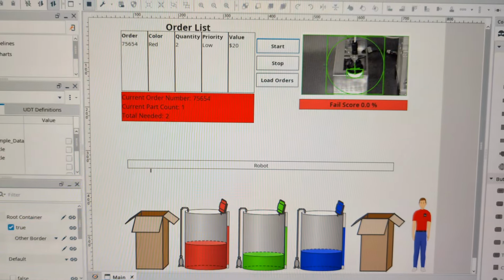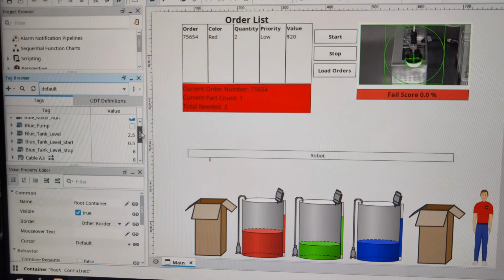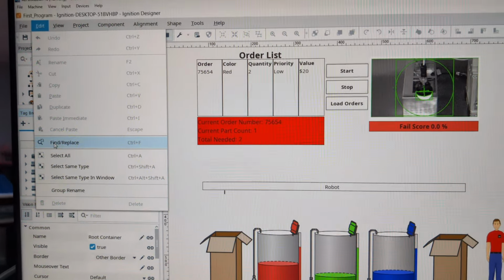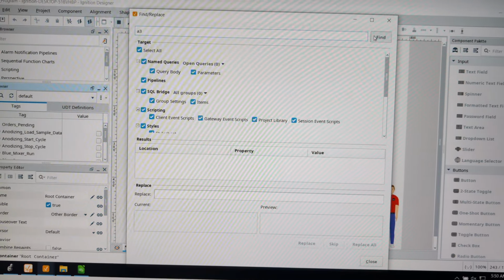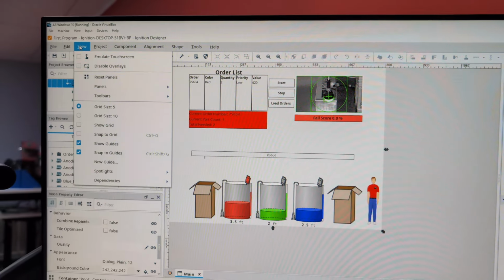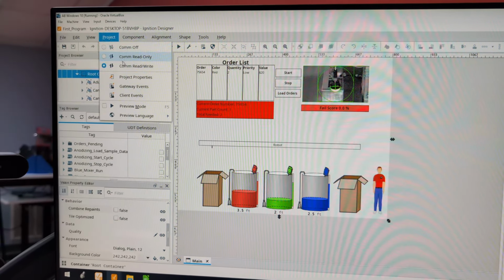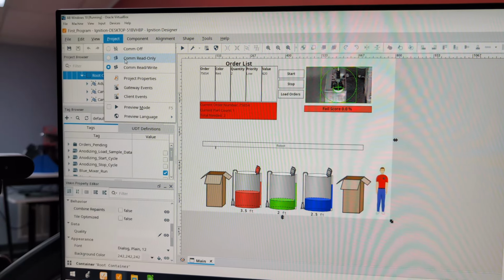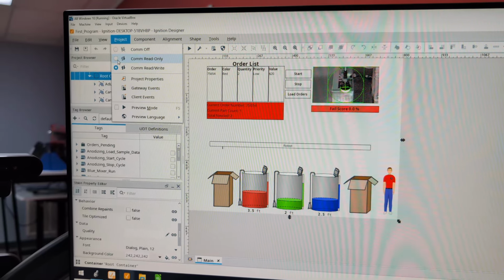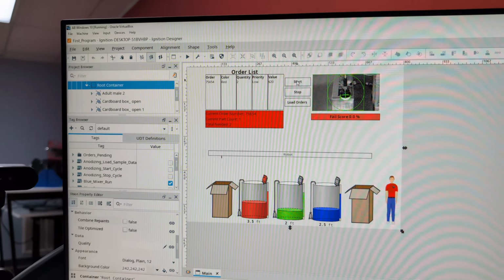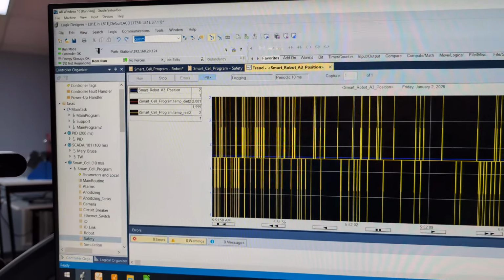Let's go over to Ignition. We know it's A3, so I'm just going to go to the edit. And we're going to find, and yeah, I'm just going to search for A3 because I believe all the instances of that would have it. Okay. So now I'd never seen a need to do this, but now would be a good time for, you know, instead of wandering through this, I should turn off the COM read write and just take it to COM read, because that'll take Ignition out of the equation. Of course, I don't have a start button now, but I can do that over in Studio.